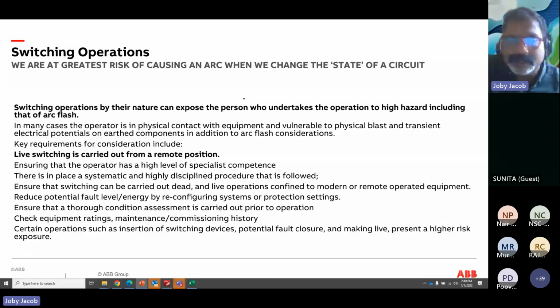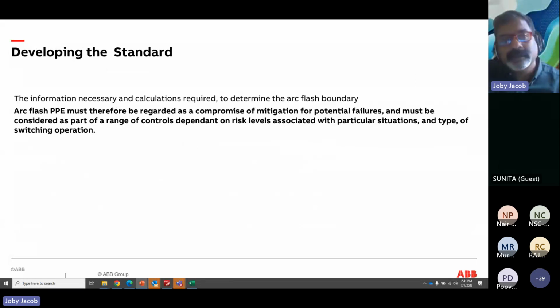Switching can be carried out dead, and live operations confined to modern or remote operated equipment. Reduce the potential fault level, and ensure a thorough condition assessment is carried out prior to the operations. Check the maintenance ratings and commissioning history for certain operations such as insertion of a switching device, potential fault closure, and exposure to such kind of crash risk. So, apart from all these engineering or design controls, arc PPE is still a must, regarded as a compromise in mitigation of the potential failure, and should be considered part of the range of controls depending on the risk level associated with the switching operations.